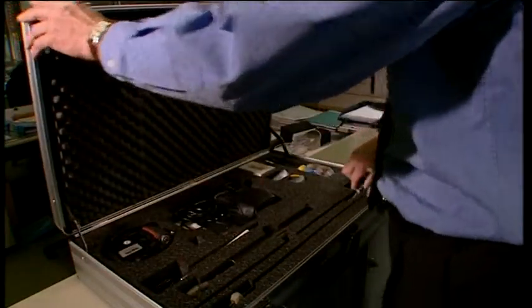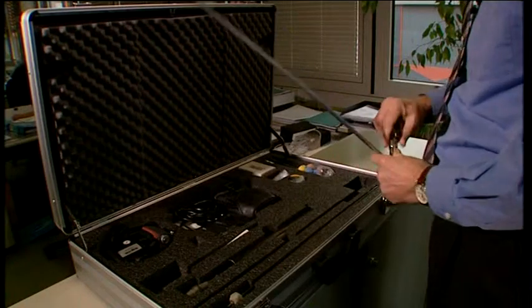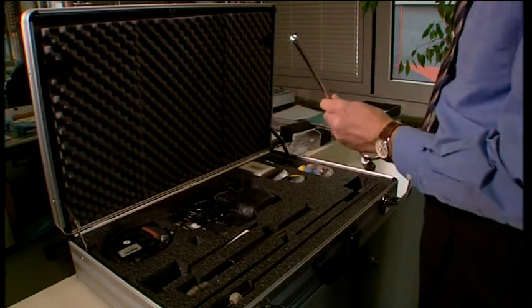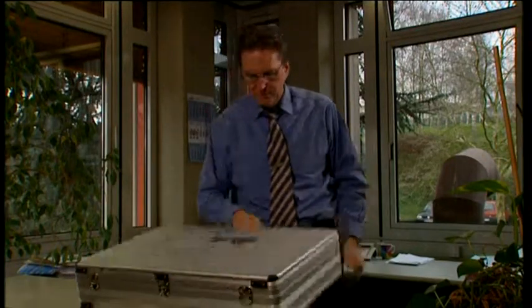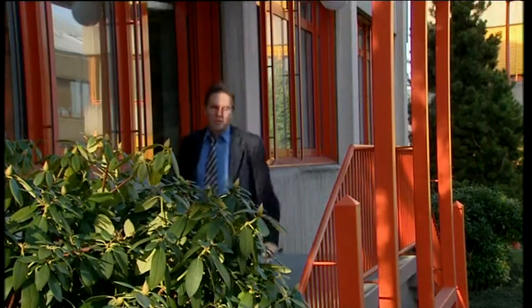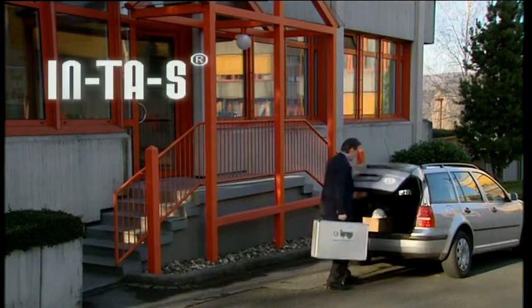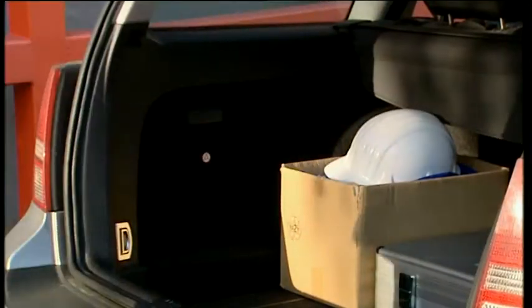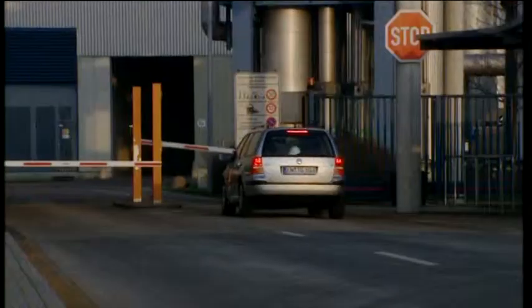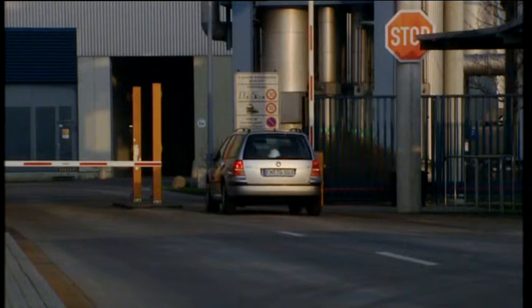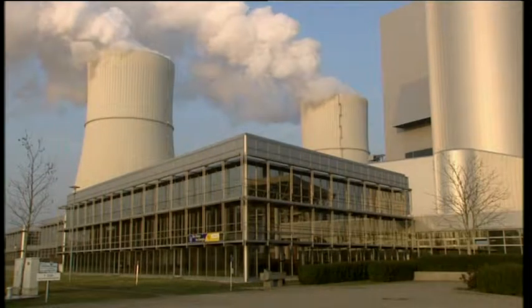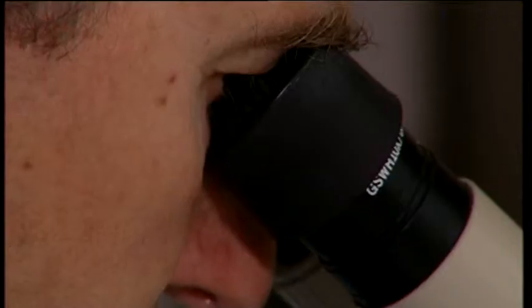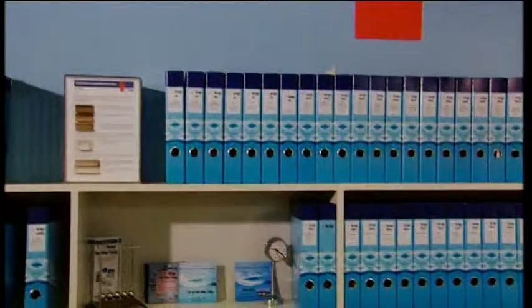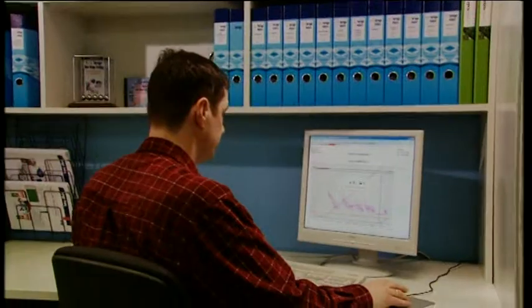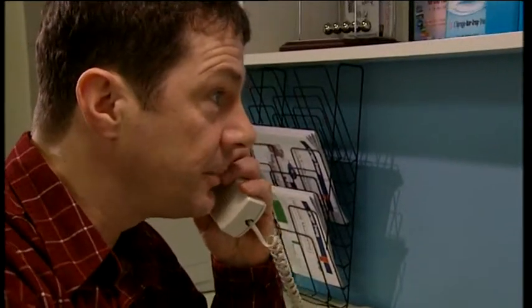To gain genuine benefits from the IN-TA-CT hardware modules, the relevant application technology is decisive. That's why we supplemented the IN-TA-CT solution, which is aimed mainly at contractors, by the IN-TA-S package, which was developed for operators. IN-TA-S stands for Integrated Taprogge Services and ensures optimized efficiency of the IN-TA-CT hardware through a whole range of services. Be it during on-site analysis of operational conditions with the operator, such as here, where tubes are being examined to select the optimal cleaning ball and cleaning frequency, or during the care and monitoring of client systems by our remote monitoring center.